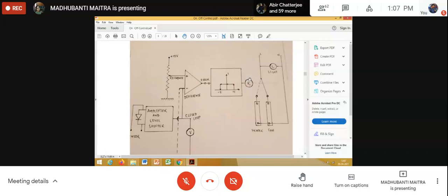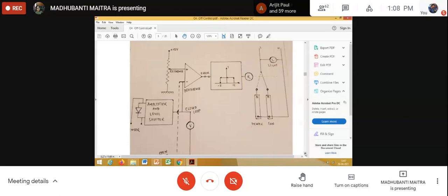If the switching frequency of the relay increases, then the life of the relay decreases rapidly. That is the problem. So to reduce the chatter of the relay, that means the on off switching of the relay, we deliberately introduce a Schmitt trigger having this kind of dead band so that the relay will not change its state at this very instant. Rather, the switching will vary from this point to this point. Am I clear? Yes, ma'am.